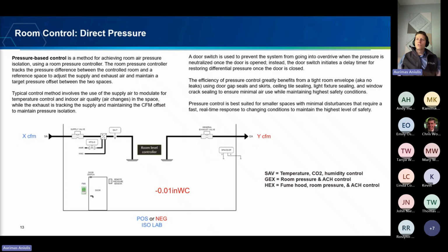The second method of control, which requires a few more pieces of equipment, is direct pressure control. So now, in addition to the supply valve, the general exhaust valve and the room level controller, we also have to introduce a door switch and a room pressure sensor to give us a real-time pressure reading across the space. This is a differential pressure reading between the adjacent reference space, typically the hallway, and the room or the zone that we're actually trying to control.